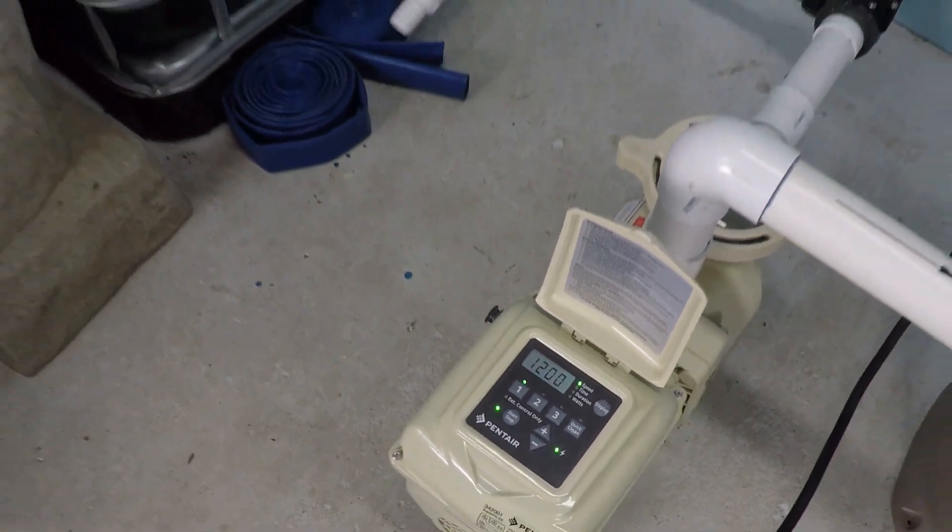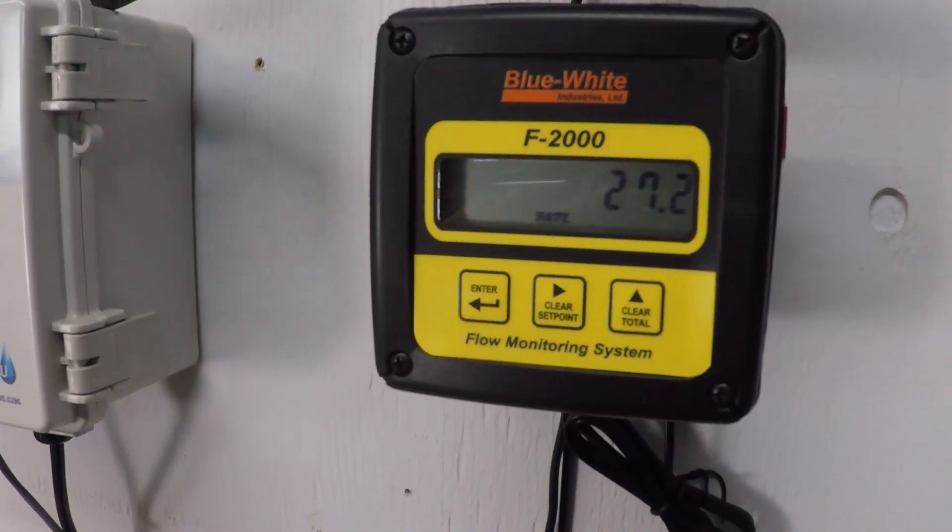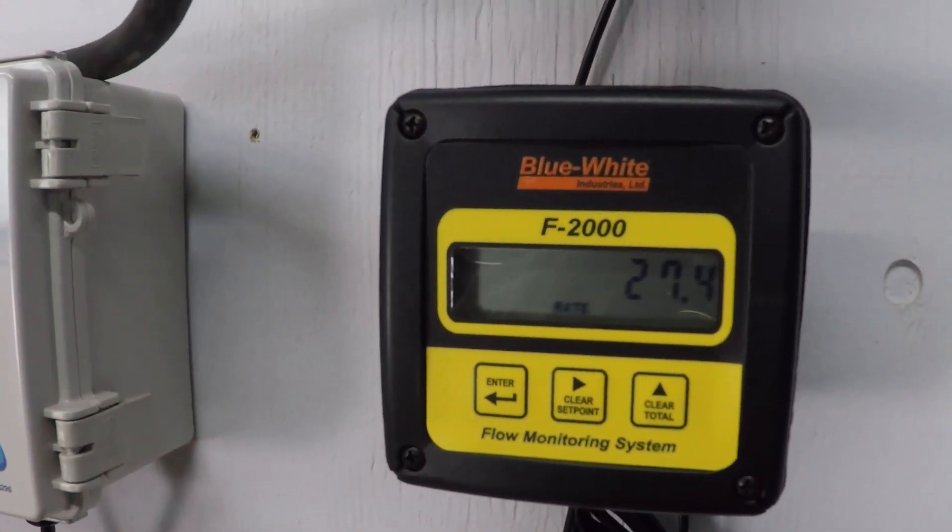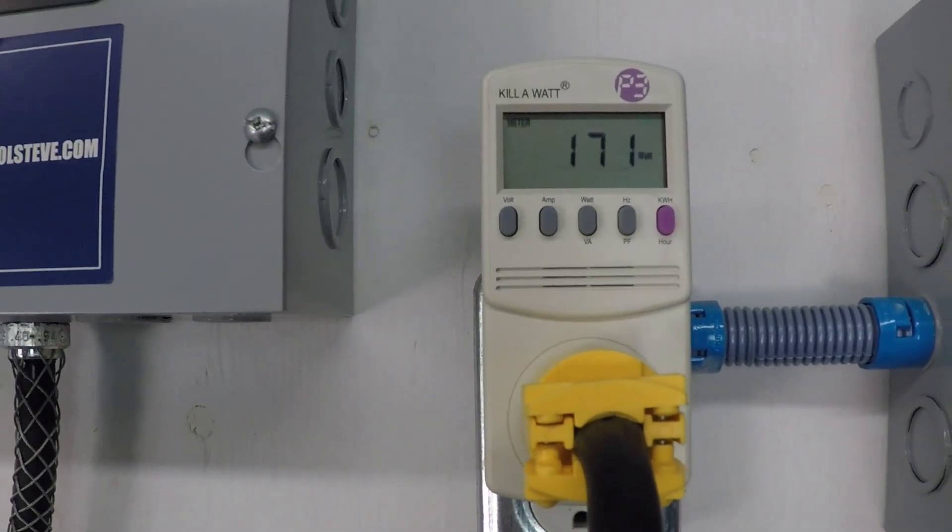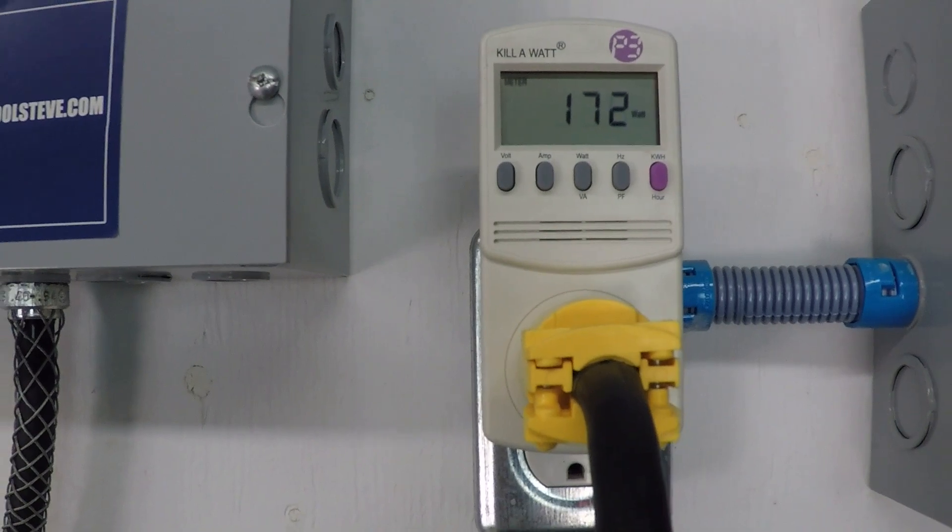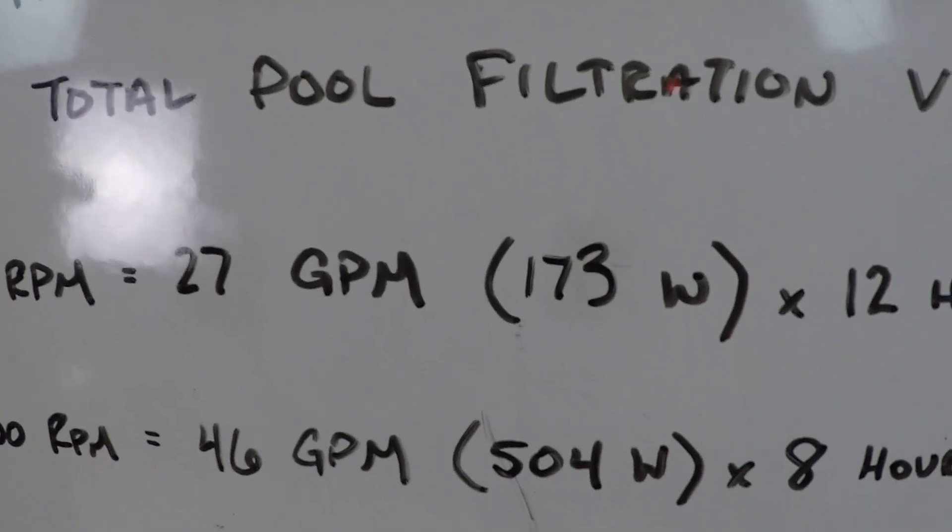We've got the pump running at 1200 RPM, just over 27 gallons per minute. Power consumption is about 173, 172 watts. And that's what we've got here.